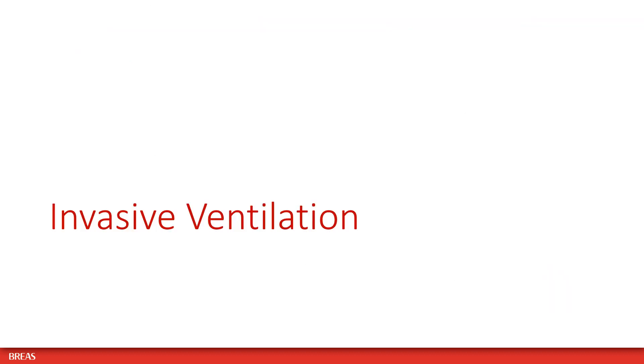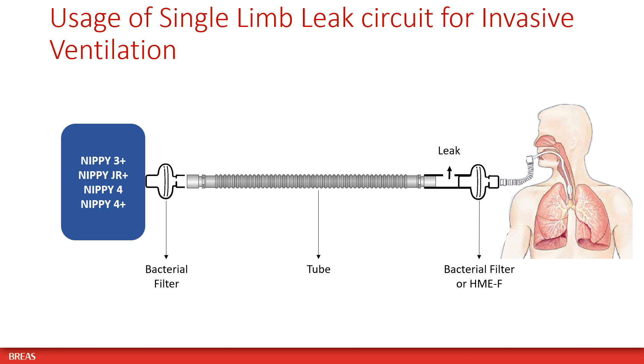Please follow these recommendations when using your NIPPY ventilator for invasive ventilation. When using a single limb leak circuit for invasive ventilation, place a bacterial filter at the air outlet of the NIPPY ventilator and another bacterial filter or HME with filter between the leak adapter and the patient.